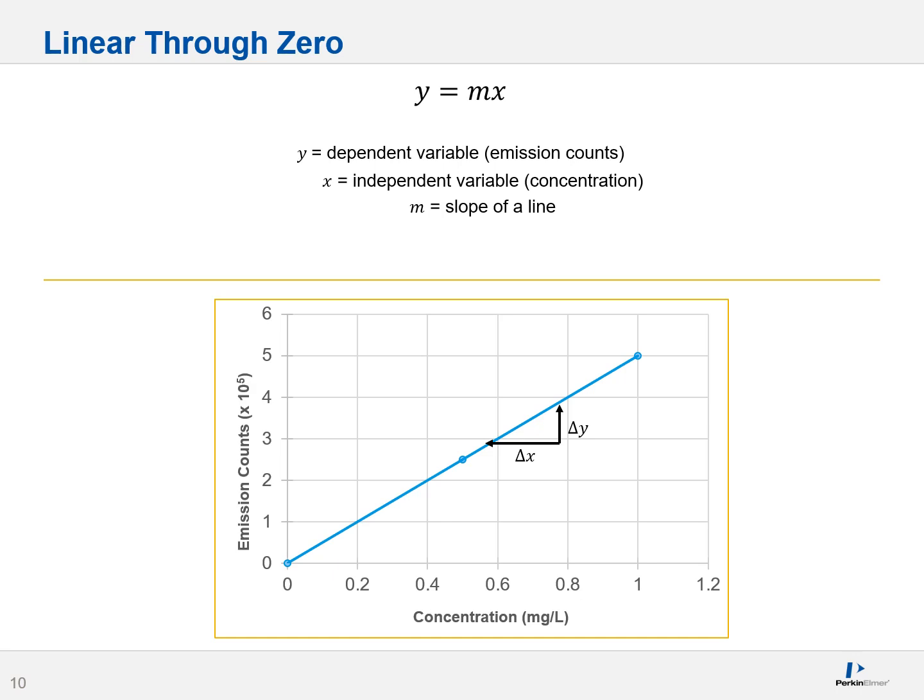In this case, you pick the better of two evils and say, hey, instead of going for inaccurate low concentrations, I'm going to go for less inaccurate low concentrations. You force it through zero. You'll find this heavily in spectroscopy-based techniques, specifically ICP-MS, ICP-OES. Not as much in other techniques.